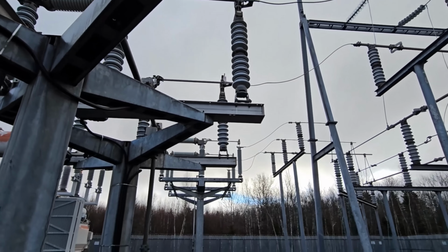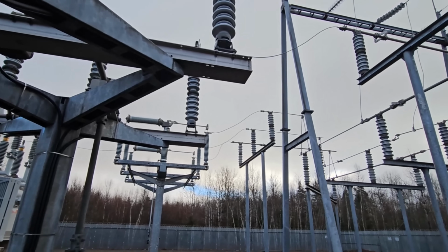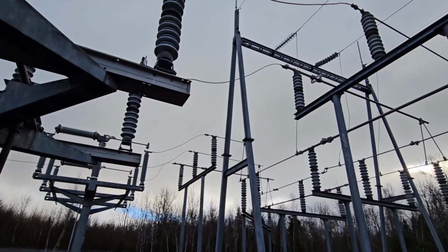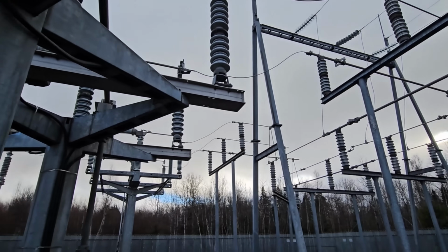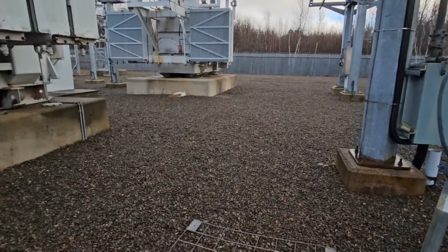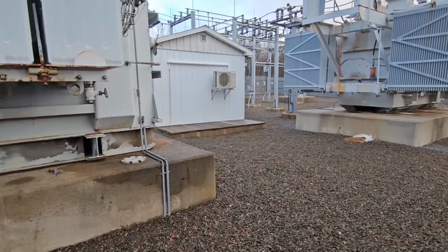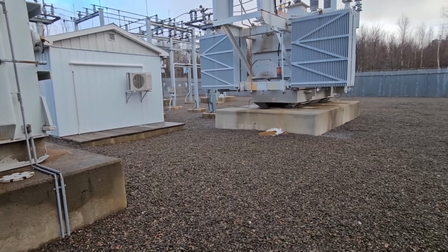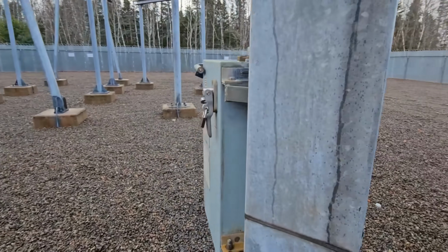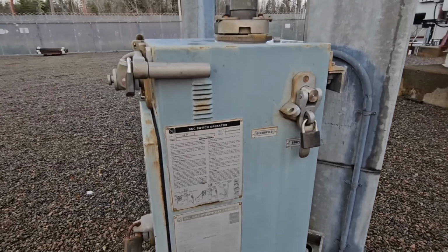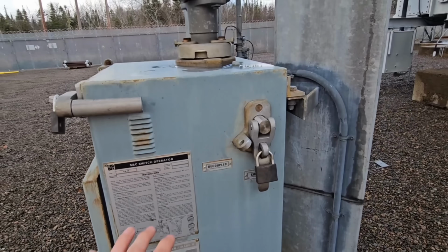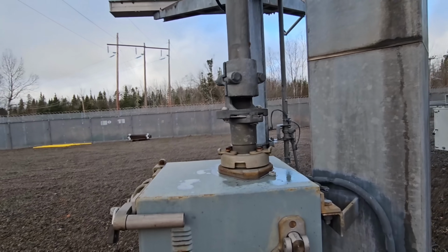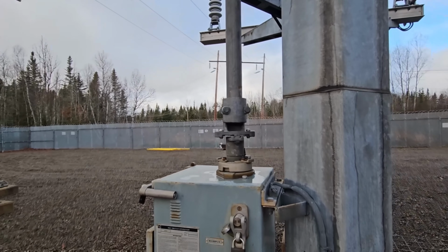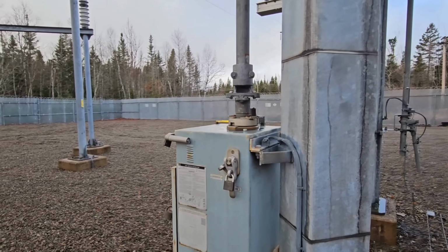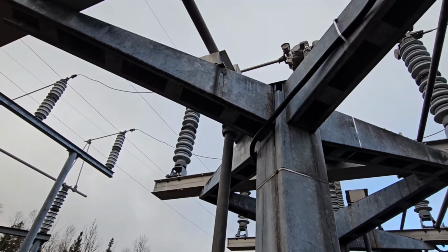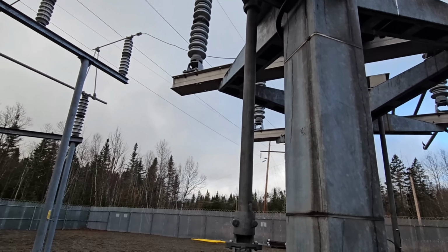Now keep in mind, probably 2 hours has gone by at this point. This stuff is all happening very fast, but in a very procedural fashion. These switches are opened electronically from inside this building right here. But this is the unit where there's a motor that allows for it to be opened. We have to disconnect the motor drive from that pipe so that in the event of an electronic failing or somebody accidentally hitting the wrong button, that's not going to close that blade in and energize this line on the guys that are out in the field working.